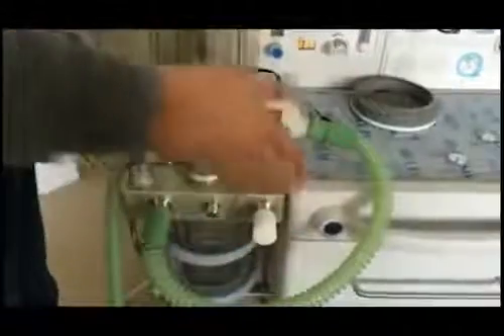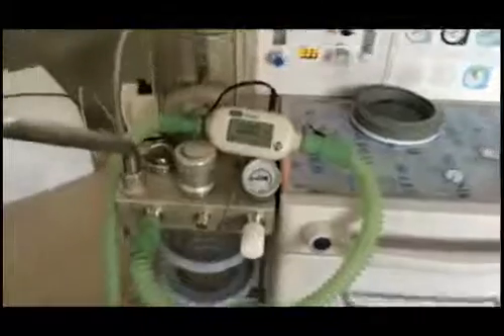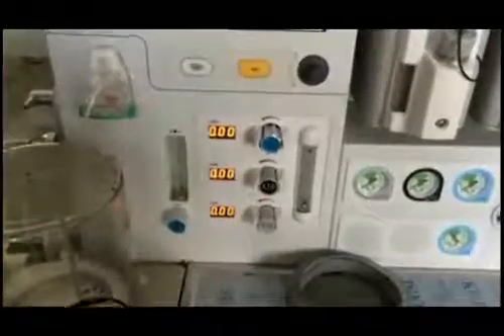After performing this action, the next step is to seal the inspiration port. Use this. After sealing the inspiration port, please use a tube longer than 1 meter and connect it to the port under the bellows, this port. After performing this, please set the flow meter to 0. Also this flow meter and this flow meter. After performing all the instructions displayed on the screen, please press the start key.